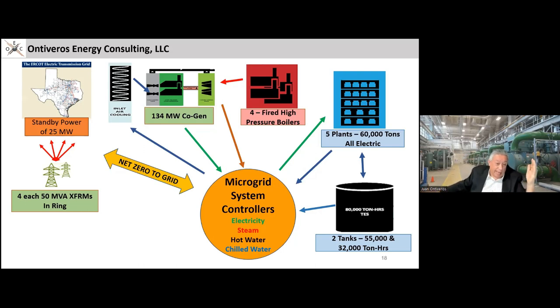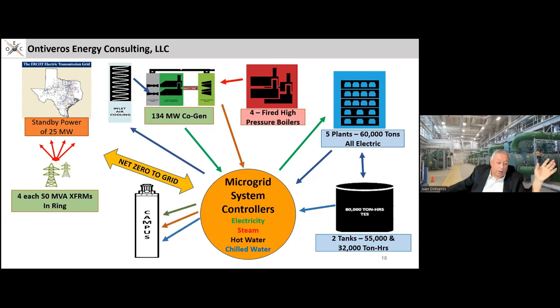So I'm saving money in gas and the combustion turbine by running it at a higher load at night. So it saves me fuel. And then I'm using that efficient cooling along with the most efficient chillers in the day to serve the system. So these are all things that you can do to operate systems. All of these services basically are behind the scenes serving the campus, heating, cooling, hot water.